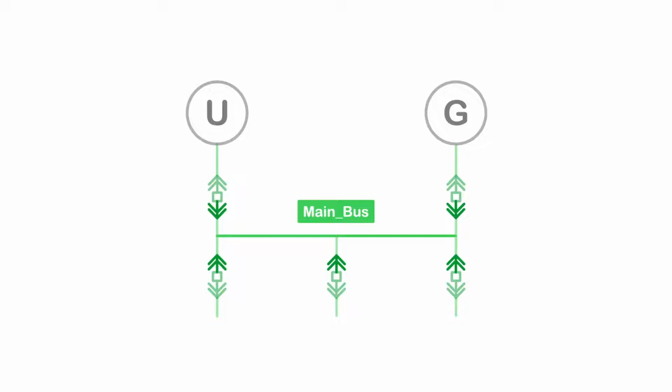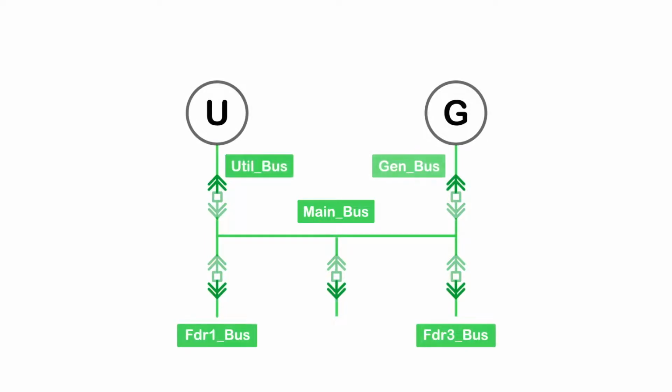If I have an entire double-ended switchgear, the entire main bus, the outputs of the main breakers, and the inputs of the feeder breakers will all have the same bus name. However, the other sides of the breakers will all have unique bus names. Understanding how these buses work electrically is critical to the advanced one-line logic. All other components just control how buses energize.